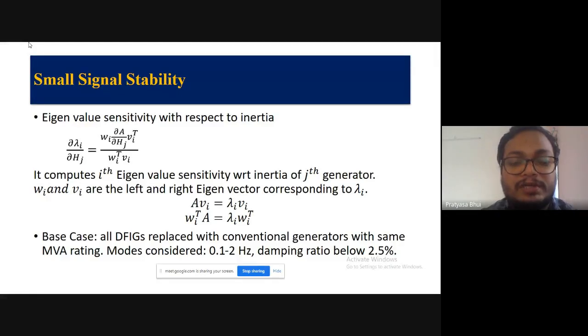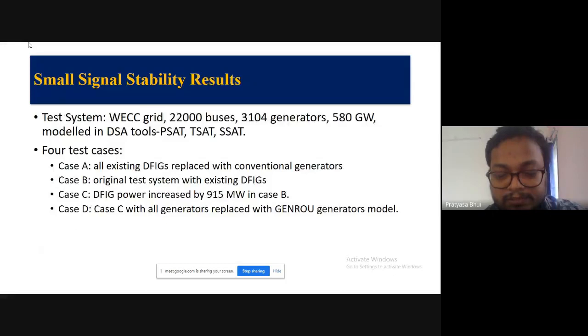Now, we can check how the eigenvalue lambda i changes with respect to inertia at the jth generator. That is the eigenvalue sensitivity, and it is given by that equation, where Wi and Vi are the left and right eigenvectors associated with eigenvalue lambda i, and the system matrix is A. So we can find del lambda i divided by del Hj. That is, how the ith eigenvalue changes if we change the inertia at the jth bus.